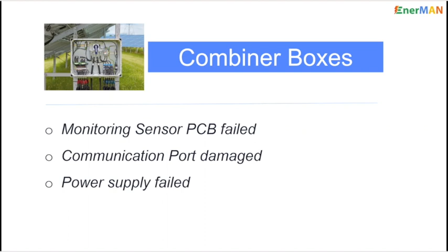The reason being these are spread across the field, and these lengthy cables are very vulnerable to noise and surges. We see communication ports damaged for the same reason, and the power supply fails again due to external surges, especially as the monsoon season approaches.